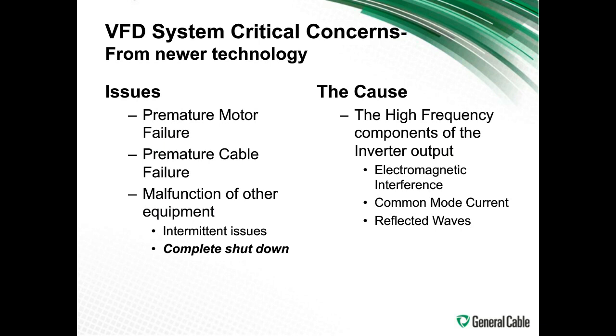So what we see in this system is critical concerns from newer technologies. You have problems with premature motor failure, premature cable failure, malfunction of other equipment, and complete shutdown possibilities. The cause is the high frequency components that the inverter from a VFD can actually provide. This causes electromagnetic interference, common mode current, and reflected waves.